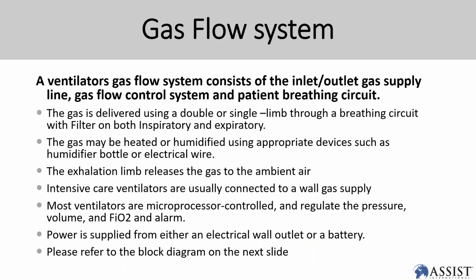Okay, when you talk about a ventilator, you need to know most of the system we are talking about is gas flow. So the ventilator system is basically an inlet and outlet of gas from high pressure to low pressure flow. So it's talking about the Y connector, single limb connection for the breathing circuit, filters on both sides, inspiratory and expiratory, and humidifier, and control volume for breathing and monitoring. So that's the purpose of the gas flow system on the ventilator.